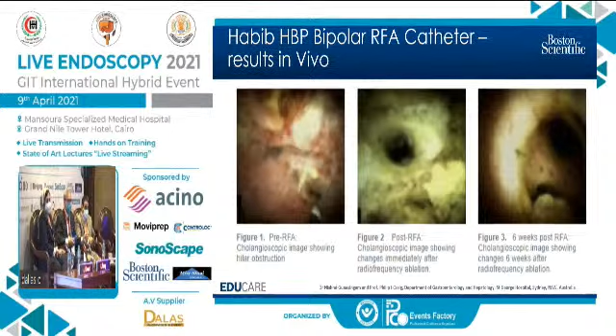Is it single use or reusable? This is a bipolar electrical probe, and it's single use because you never know once the isolation would fail and cause electrical damage inside the body of a patient. So that's why it's single use. Do you use this probe through the spyglass or through the scope? It's an 8 French catheter, so it fits through a duodenoscope, but not through a spyglass scope.